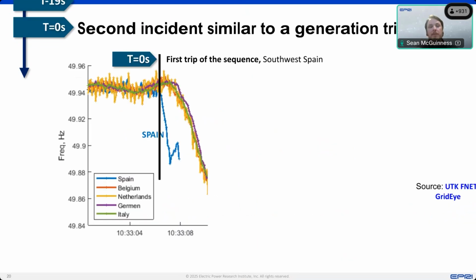So the main event really then kicked off as we label it here at t equals to 0 seconds. So this is the first tripping. It's of a large generator in southwest of Spain, and you can see quite a substantial drop in frequency. But you can also see that the Spanish frequency fell a lot faster than the measurements elsewhere in the European grid. So this is where we began to see the loss of synchronism between Spain and between the Iberian Peninsula and Spain and Portugal and the rest of the European grid. So this opening up of the frequency or loss of synchronism would then trigger power swings and heavy loading of the lines in between the two areas. And then this is where really we begin to see the disturbance really getting going.